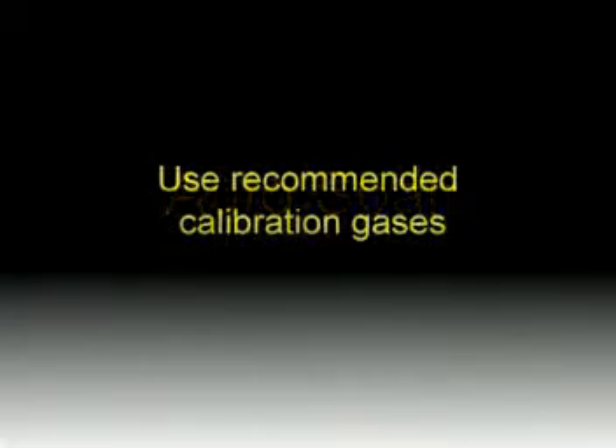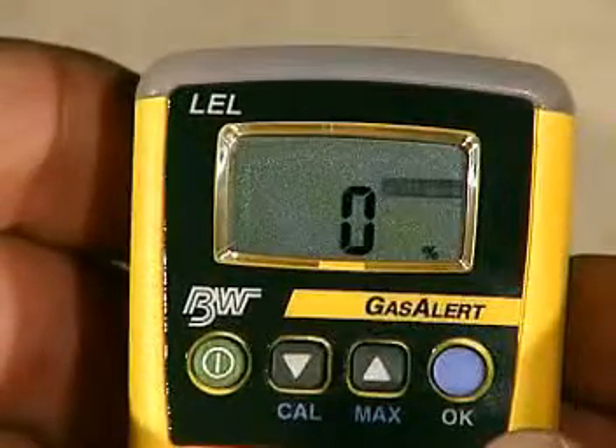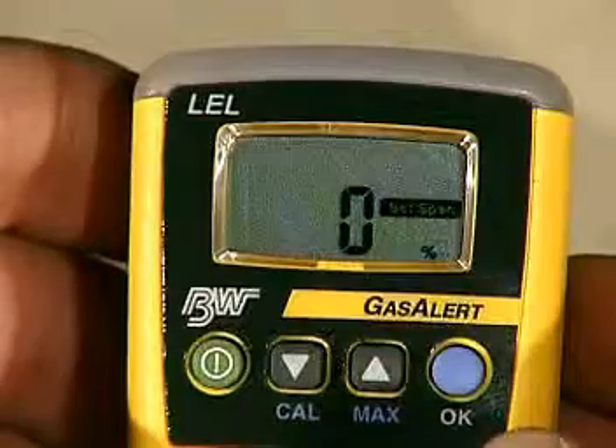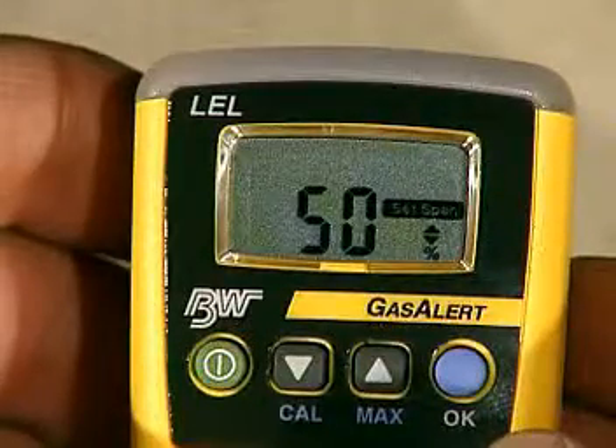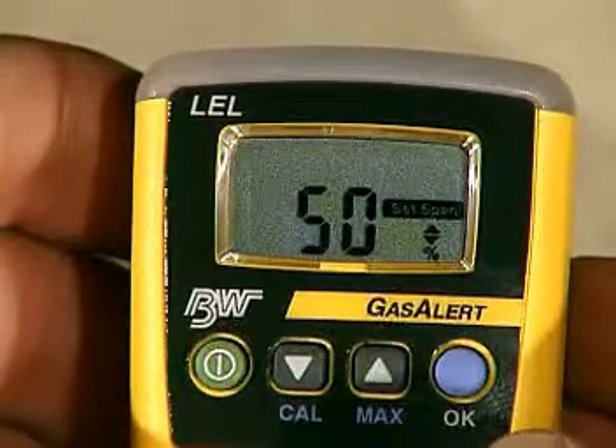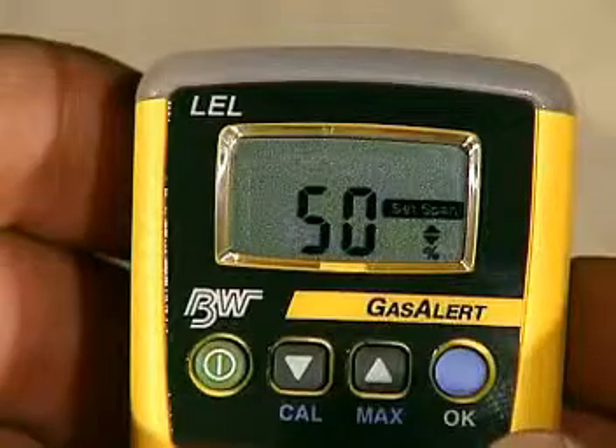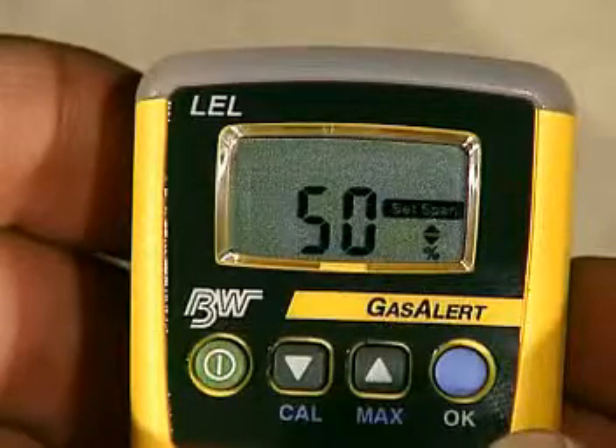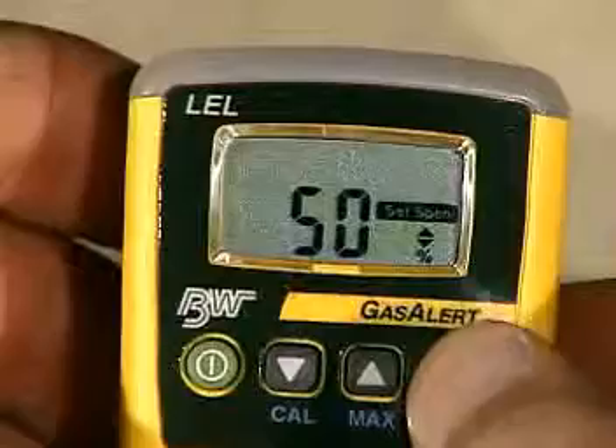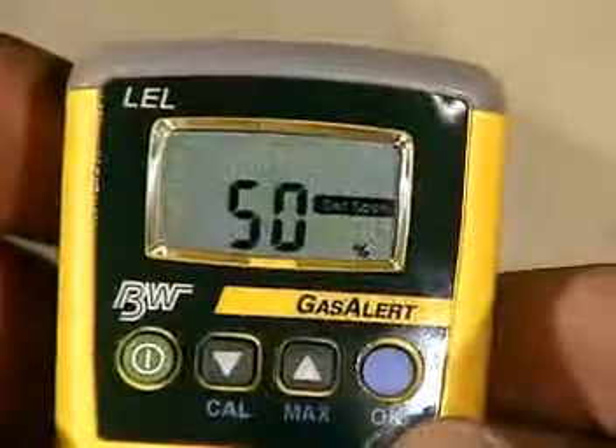GasAlert-LEL span is virtually automatic. If the passcode protect function is activated, enter the passcode when requested to proceed. Use only recommended calibration gases. Set span and the expected calibration gas concentration appears. The up-down arrows flash, prompting you to either input a new gas concentration or confirm the displayed value. Let's press OK to save the displayed value.